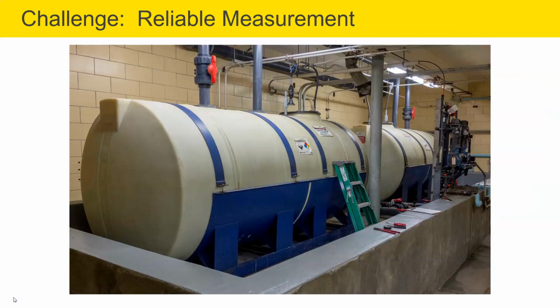The next major challenge is getting a reliable level measurement. Some of the chemicals in these tanks are just simply nasty, and a lot of the times they are put in plastic tanks because of how aggressive the chemicals are. Take ferric, for instance. Most ferric tanks out there are so stained you can't even see through the tank wall to get a visual level indication.